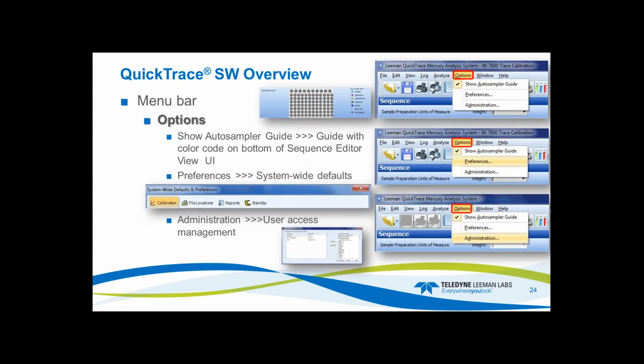On the Options drop-down menu from the menu bar, you can show the Autosampler guide, and that's a color-coded guide that shows up on the bottom of the sequence editor, because that's where most of your samples are added, via the sequence wizard or manually. So you get a nice color code of what's happening, whether it's sample, quality control, spikes, and so forth. All these color codes will be active when it goes into the Autosampler guide. You can also print that guide as well and take it to the fume hood so you can load your samples into the rack, and that helps with avoiding mistakes.